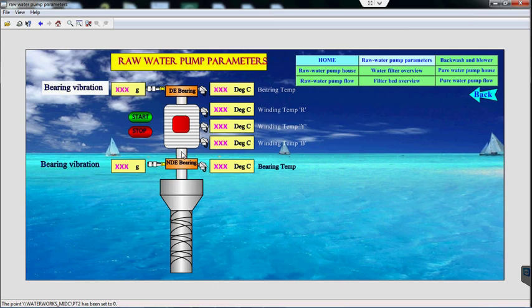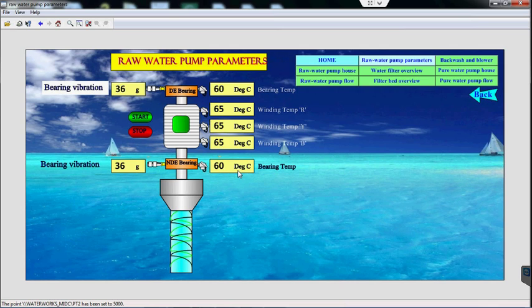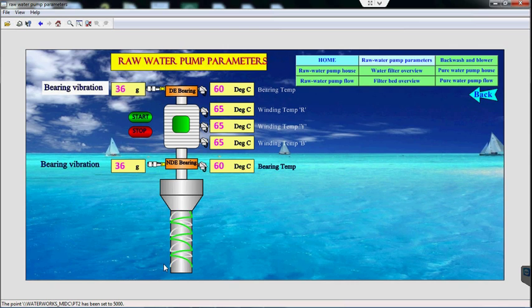Let us understand raw water pump parameters. Raw water pump safety is ensured by measuring the pump bearing vibrations, pump bearing temperature, and motor winding temperature. These parameters are recorded in SCADA. In case pump vibrations or bearing and motor winding temperatures exceed the allowable limit, an alarm will be annunciated to alert the operator to take precautionary action. These parameters can be further used for a machine maintenance monitoring system.